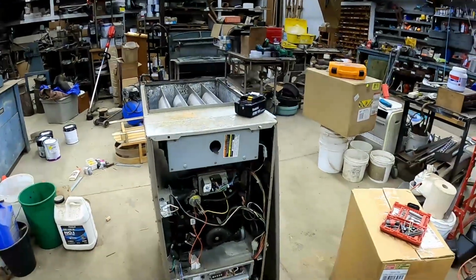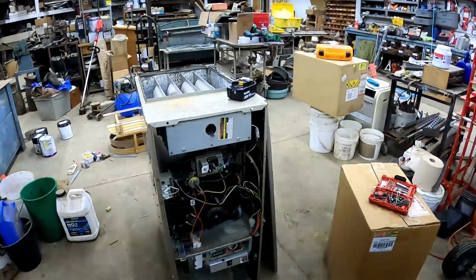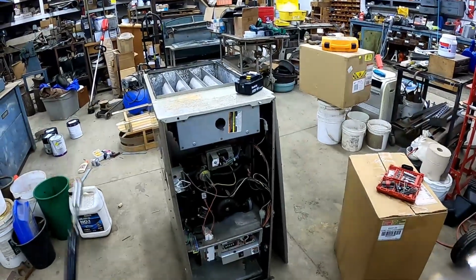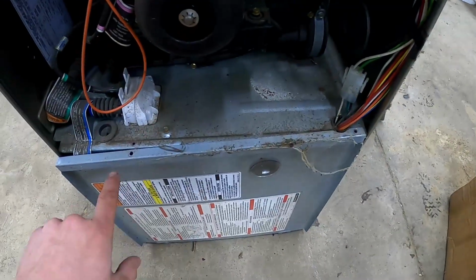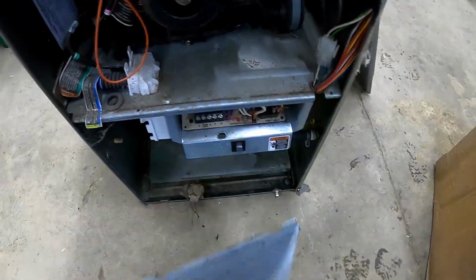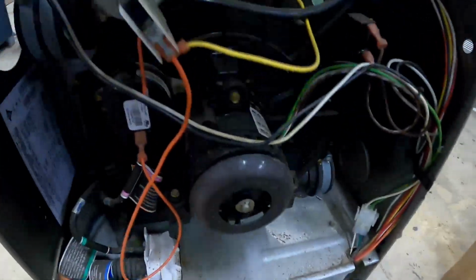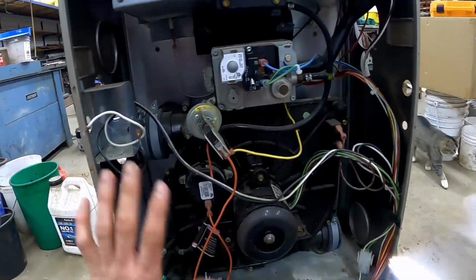Today we are going to be replacing the heat exchanger on this Payne furnace. Payne is a branch of Carrier, so it's pretty much the exact same as most Carrier units. So the first thing you're going to want to do is remove these two screws and pull this panel off of the front. And next we have to get pretty much everything out of here.